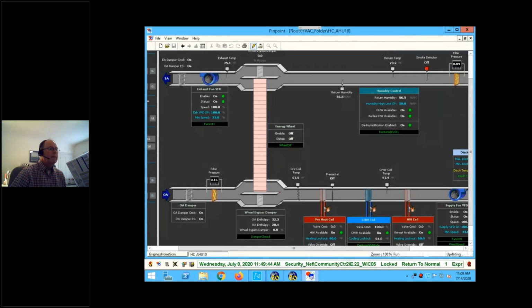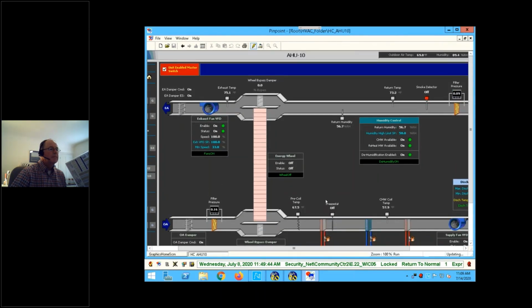It doesn't call for it to be open, but our outside air humidity is pretty high too, at 90%. Okay, so we're going to go through the wheel even when we're not in economizer then. That's right, yeah.